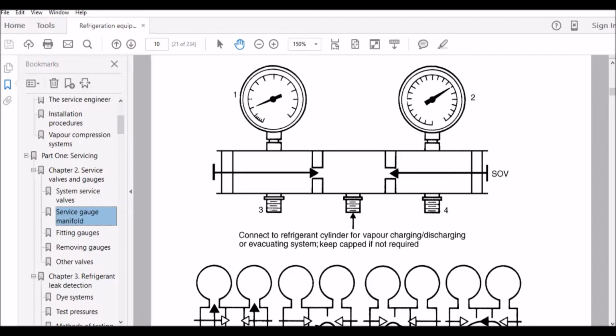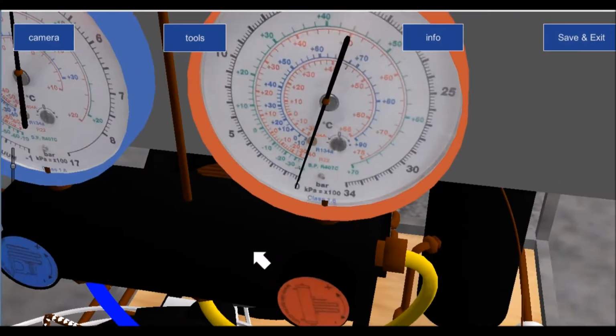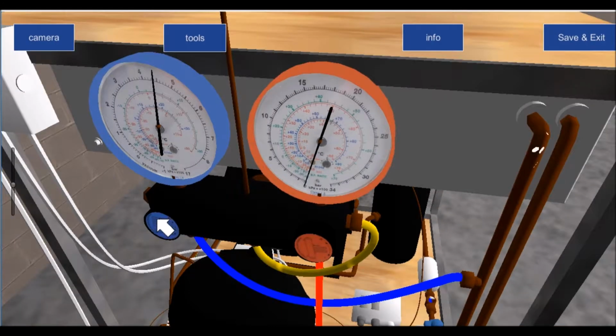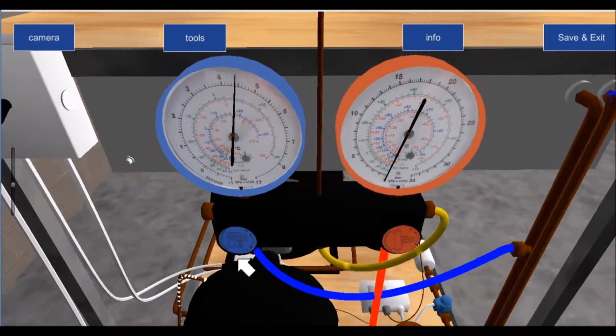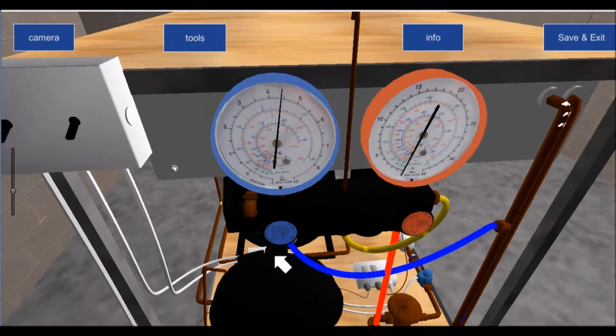Now, if I had made the mistake of opening this actual valve, so this shut-off valve, all right, the low side shut-off valve, if I made the mistake of opening that, refrigerant would have entered into this manifold here and leaked out to the yellow hose line.